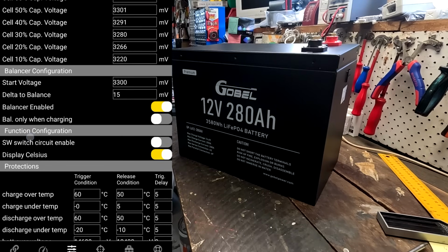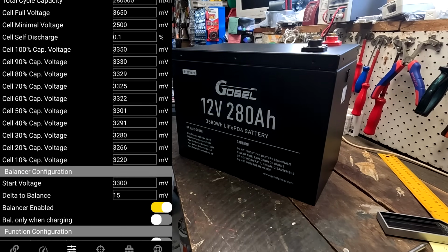Glad they didn't lock down the BMS here, so we can actually adjust these parameters. I would set the balancer start voltage here to 3.45, maybe put the balance delta down to 5 millivolt, but everything else is fine with me.